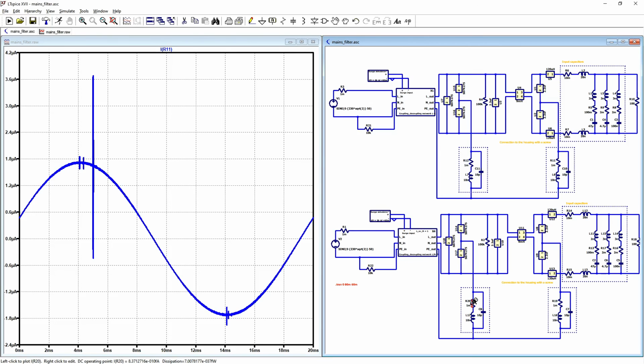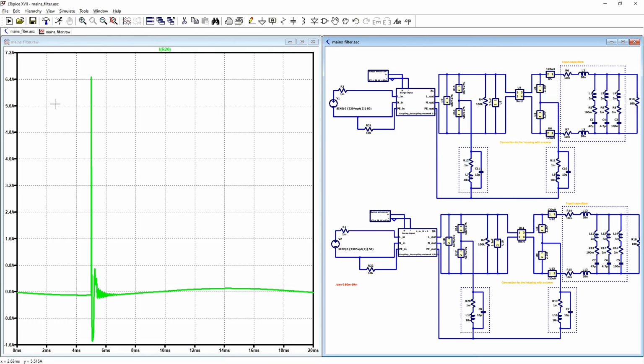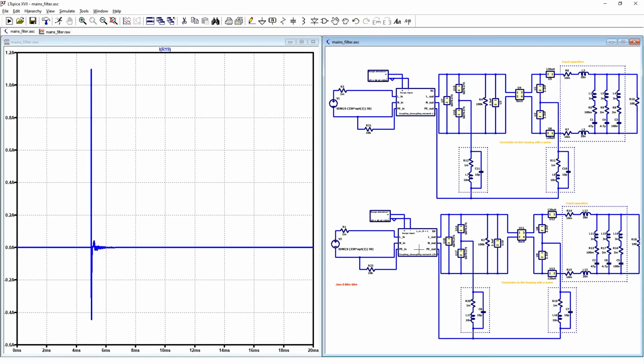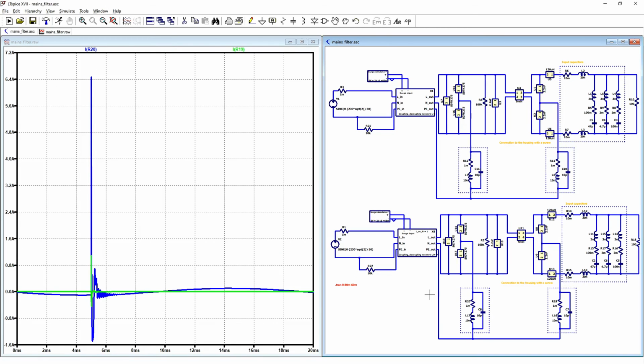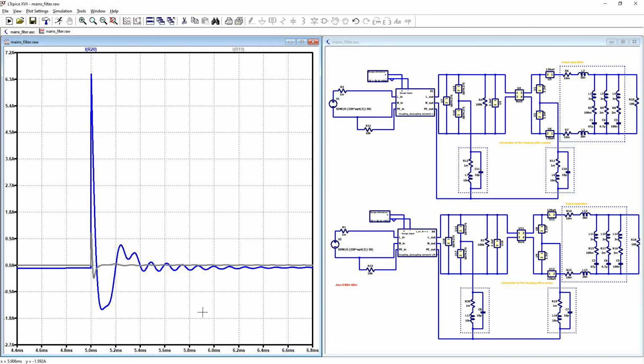But for the common mode surge pulse, we can see that there is amperage here, 7.2 amperes, and here it's a little less because it's after the first part of the filter, so it's 1.2 amperes, but still in amperes. We can say that our pulse is really going through the screws, and this is how it looks. This is the conclusion of my video.